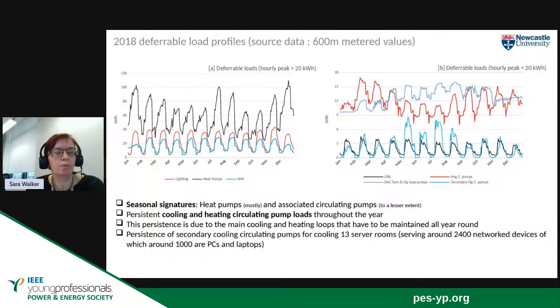So I did mention that we looked at other loads, and this shows some of that. To mention the secondary cooling and the primary heating circuit, the circulation pumps and so on, then the heating pumps in terms of circulation are, obviously, more available in the winter months, less available in the summer. That's the red variation here. And then the cooling circuits are more available in the summer for demand response and less available in the winter. We did look at some demand response for the lifts, because we have a number of lifts in the building, so we could turn 3 of those off and still have enough lifts and offer some demand response there.